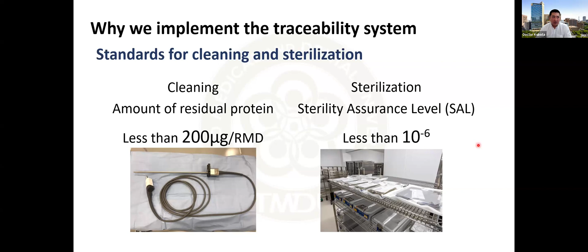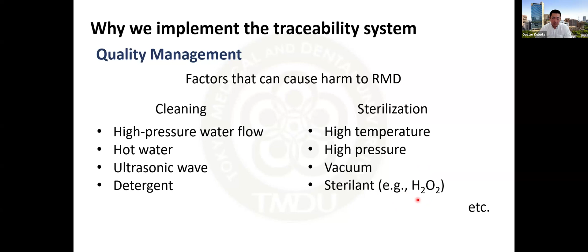And it's not enough for an instrument to be sterile. It has to be in proper working order, meaning it has to be able to perform its function and performance without problems. Not only use, but also reprocessing can cause deterioration. For example, in cleaning, high pressure water streams, hot water, ultrasonic waves, and detergent are considered damaging factors. If the detergent is not sufficiently rinsed, it can cause corrosion, clogs, and pitting on the instrument. In sterilization, in addition to high temperature and high pressure, some sterilization methods create a vacuum during the process. So the vacuum and sterilants, such as hydrogen peroxide, can affect the instrument. The work must be performed in a process that has been verified for compatibility with the instrument.